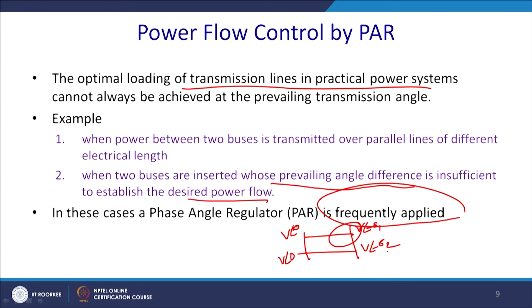So, one will supply power at angle delta 1, assume that it is 0, and if it is V 0, it will be minus delta 2. So, there you require a phase correction, because the angle difference is insufficient to establish the desired power flow, as someone will carry more current and someone will carry less current. In these cases, a phase angle regulator or PAR is frequently applied to make their phase voltage angles the same.